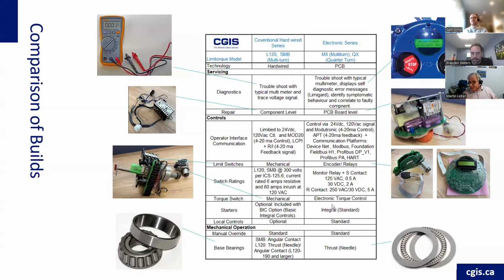The basic controls you need to start an actuator are standard on the electronic series, but optional on the hardwired series, because the L120 was developed back in the 80s to compete for the power industry, where they were placing the starters in a remote location in a room. So if you had 30, 40, 50, 100 actuators, you'd have a panel with your starter circuit in there, so you could walk in and say, that's the starter circuit, let's troubleshoot that. It was very modularized, so that starter assembly could be located remotely.